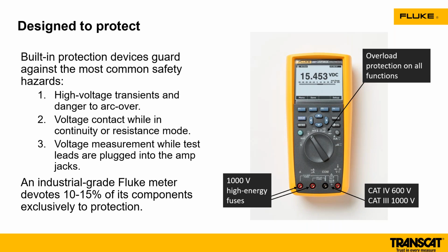Fluke literally devotes 10 to 15% of all the components in its meters exclusively to protection. That's huge. With the category rating, we can run our meter through and do testing. There are videos on YouTube where we've taken our meter and tested it at 8,000 volts, ran a transient through it in our lab, and it handled it, versus other products that are not designed for it. They say they're designed to it, but they didn't. So it's a key win again to make sure you have the right meter for the right job.